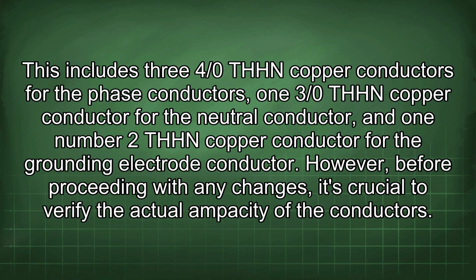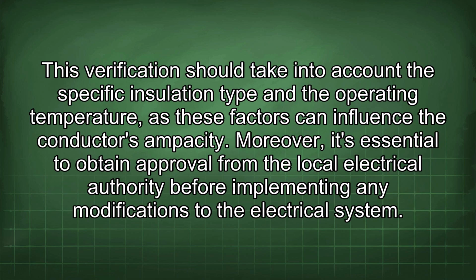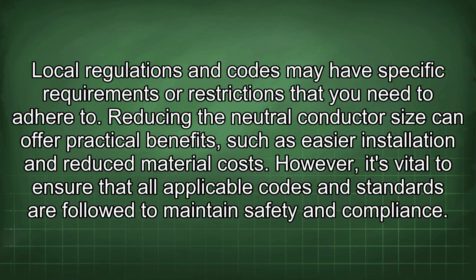However, before proceeding with any changes, it's crucial to verify the actual ampacity of the conductors. This verification should take into account the specific insulation type and the operating temperature, as these factors can influence the conductor's ampacity. Moreover, it's essential to obtain approval from the local electrical authority before implementing any modifications to the electrical system. Local regulations and codes may have specific requirements or restrictions that you need to adhere to.